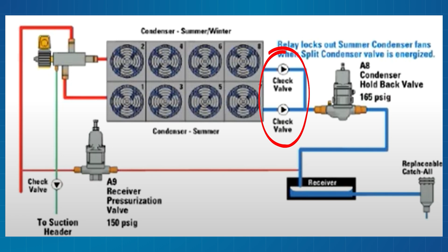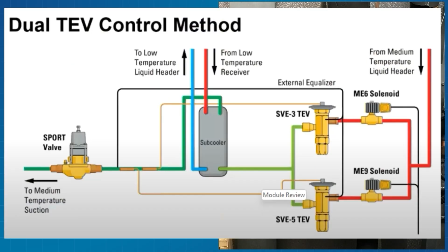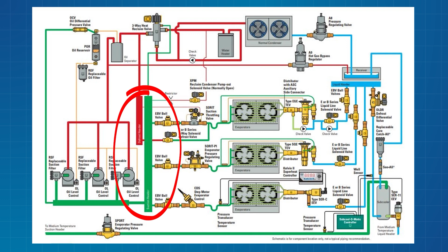We got our liquid coming out of here and going into our dryers. We went through our sight glass, which is normally on the other side of our subcooler. We went through the subcooler itself and all of its different configurations. Then we came up into our liquid header, came down our liquid header, and went through our solenoids, our expansion valves, our distribution system, our evaporators, and our EEVs and EPRs into our suction header. That leaves us back at our compressor.